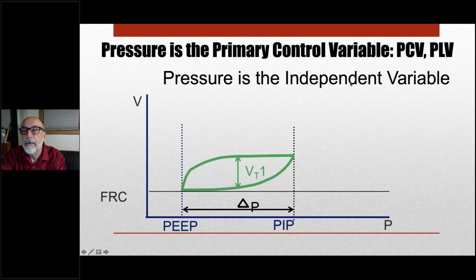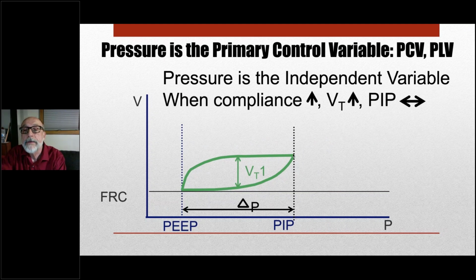In contrast, when pressure is the primary control variable, again, here's our pressure volume loop, pressure, volume. When compliance increases, the pressure now is fixed here. So what will happen, of course, is that volume goes up. Now, that may be a good thing if the lungs were stiff and tidal volume was inadequate, but if we selected an inflation pressure that was appropriate to deliver a normal tidal volume and then compliance improves, we could now have excessively large tidal volume with lung injury and hyperventilation. So this is, of course, potentially dangerous.